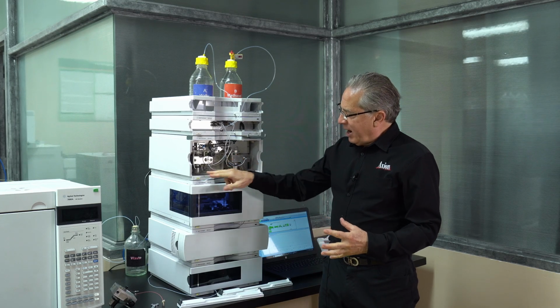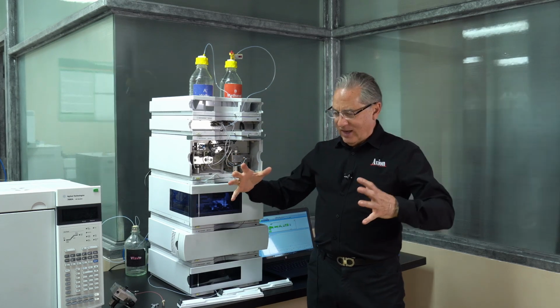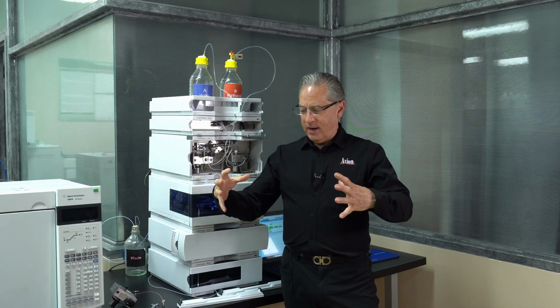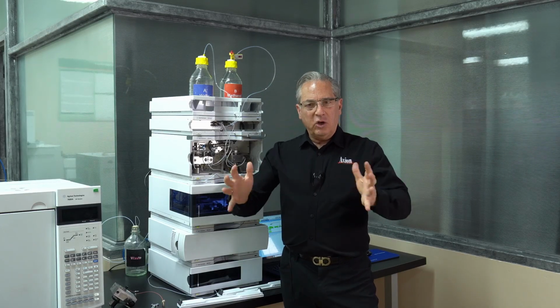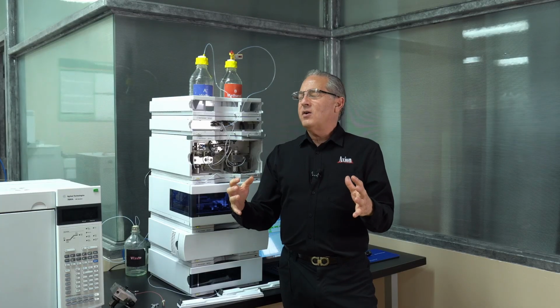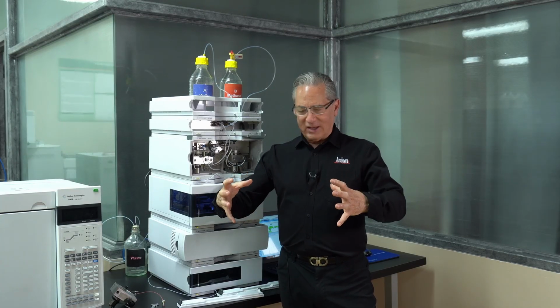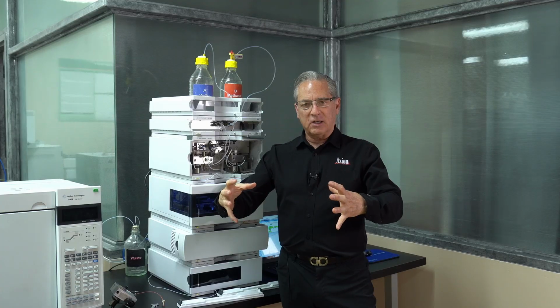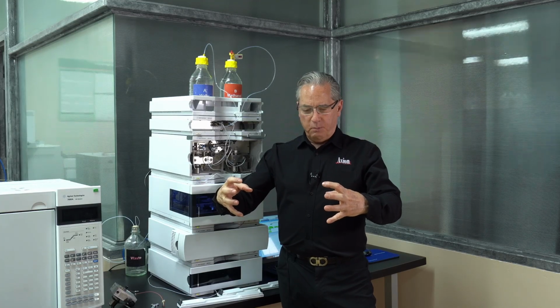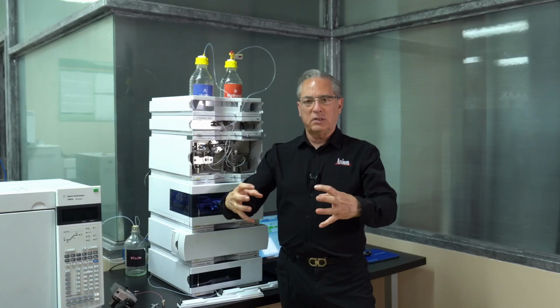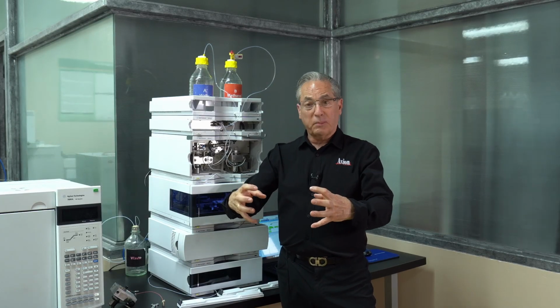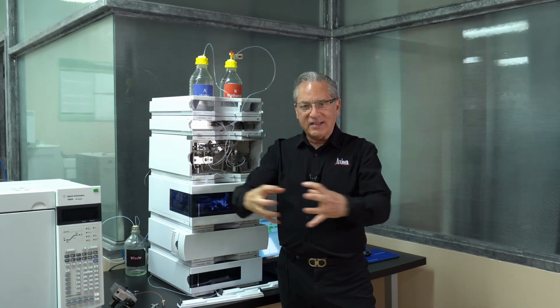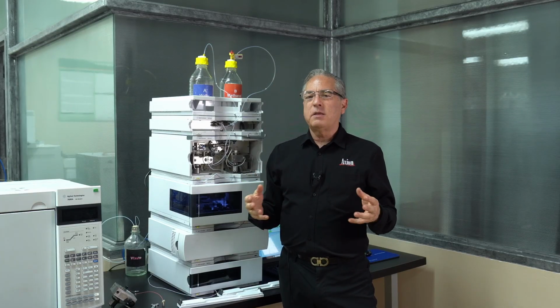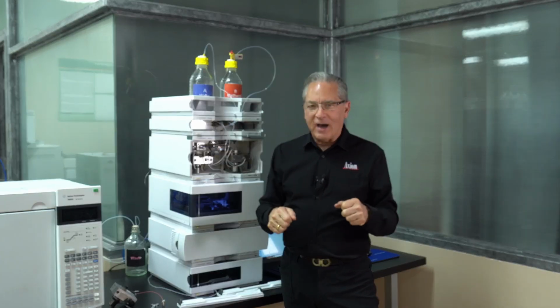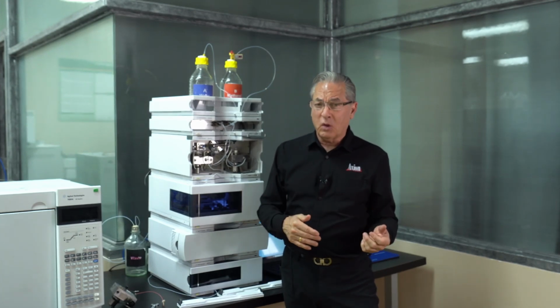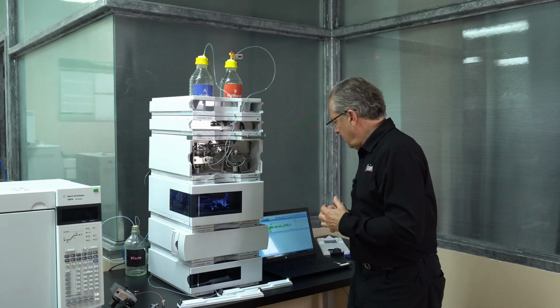So what happens when an air bubble gets in? Remember, air is compressible. If I take air and increase it from 0 to 1,000 psi, I could do that. Liquids are only very slightly compressible. If I take water from 0 to 1,000 psi, it compresses about that much. The pump is designed to pump things that are not compressible. It knows liquids like acetonitrile, water, and methanol, whose compressibility is very low. If something gets in there that compresses, it drives the pump nuts. Either the pump will just not work, it moves but nothing comes out, or something comes out but it's not reproducible. So you never want to operate with an air bubble in the pump.